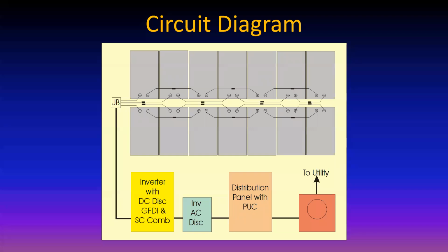All right, so then down the string to the inverter, it's got a DC disconnect, it's got ground fault detection interruption, it's got source circuit combiner, it's probably got arc fault protection as well. Then the output goes to an inverter AC disconnect to a distribution panel, with the point of utility connection then in the distribution panel by a backfed circuit breaker.